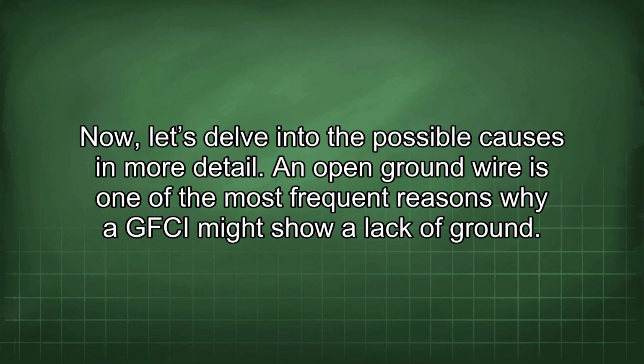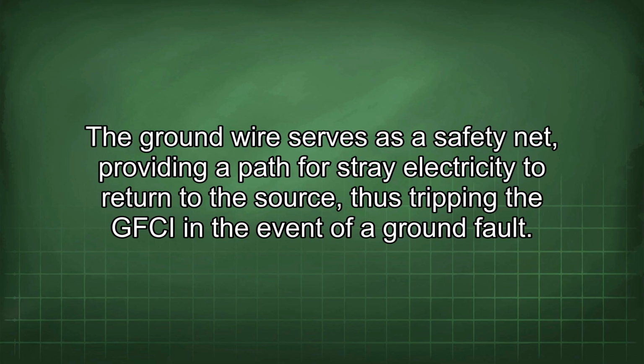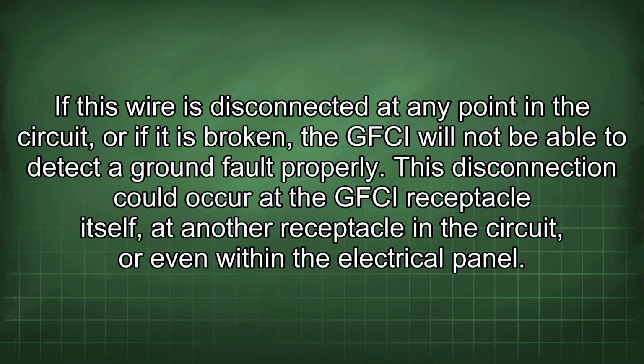Now let's delve into the possible causes in more detail. An open ground wire is one of the most frequent reasons why a GFCI might show a lack of ground. The ground wire serves as a safety net, providing a path for stray electricity to return to the source, thus tripping the GFCI in the event of a ground fault. If this wire is disconnected at any point in the circuit, or if it is broken, the GFCI will not be able to detect a ground fault properly.